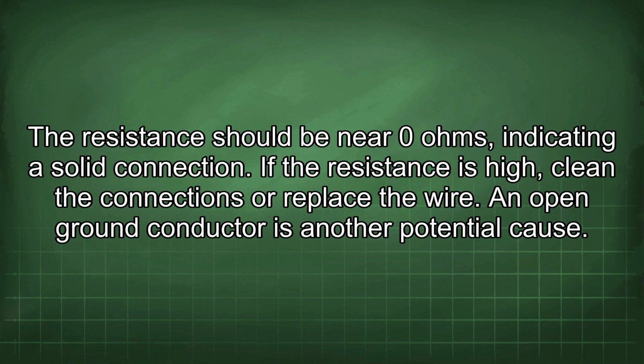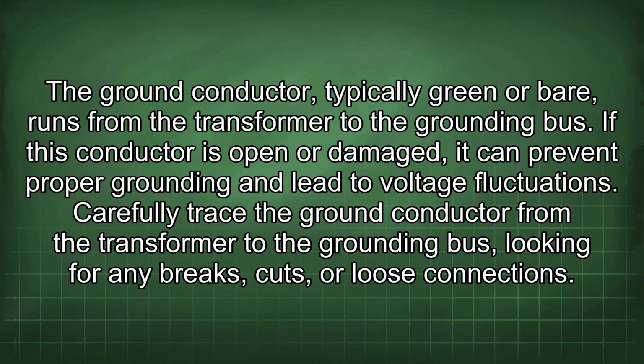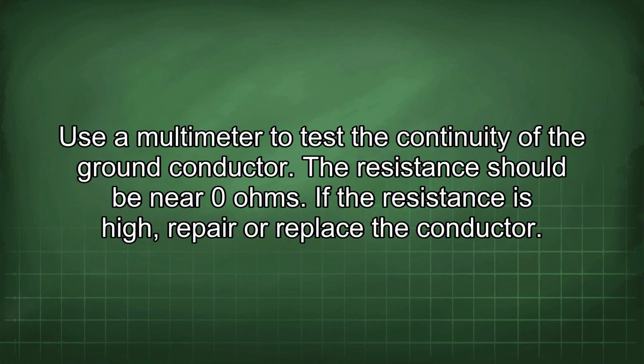An open ground conductor is another potential cause. The ground conductor, typically green or bare, runs from the transformer to the grounding bus. If this conductor is open or damaged, it can prevent proper grounding and lead to voltage fluctuations. Carefully trace the ground conductor from the transformer to the grounding bus, looking for any breaks, cuts, or loose connections. Use a multimeter to test the continuity of the ground conductor. The resistance should be near 0 ohms. If the resistance is high, repair or replace the conductor.